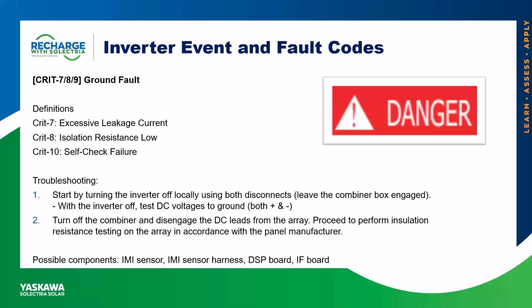During testing, since you will need to open the inverter, it is in your best interest to perform a visual inspection of the cabinet interior to verify nothing is obviously damaged. And as mentioned previously, there are internal grounding connections that need to be properly seated. Referring back to our optional equipment list, we did recommend a megohm meter be brought to site. In this event, it would be very useful to avoid a revisit, such that you can test the insulation resistance on the DC conductors, provide those results, and then we can proceed accordingly from there.